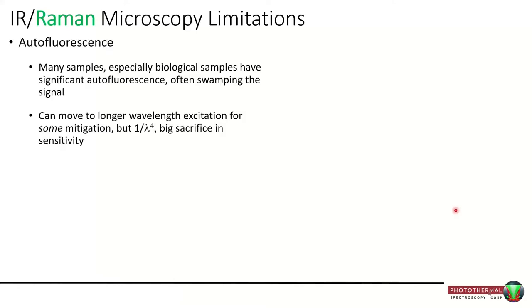Moving to Raman microscopy, that has a whole host of other limitations. Anyone who's used a Raman microscope will tell you the number one issue is autofluorescence — many samples, especially biologicals, have significant autofluorescence that often swamps the signal. One approach is to move to longer excitation wavelengths, such as 785 nm, but that comes with a massive sacrifice in sensitivity because of the one-over-lambda-to-the-fourth relationship — as the excitation wavelength gets longer, sensitivity drops off very quickly.